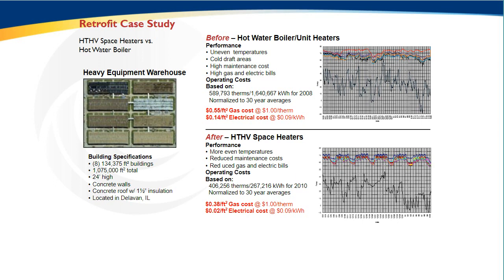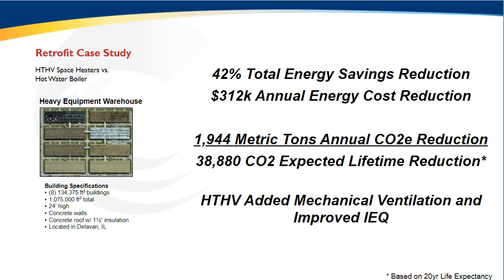And what they saw was they actually retrofitted the entire building with a decentralized HTHV space heater system with more even temperatures, forced mechanical ventilation, and by utilizing the zones and high velocity, they were able to get much more even temperatures, such that they saw a massive reduction in gas and electrical bills. What this facility saw was about a 42% total energy savings reduction. These dollars are quite substantial. Granted, this is a pretty large facility, about 1 million square feet. However, they saw about $312,000 of annual energy cost reduction. And from an emissions perspective, they had almost 2,000 metric tons of CO2 equivalent emission reduction by utilizing the decentralized HTHV system. So again, key theme, added ventilation, improved the indoor air quality, and massive reduction in energy and emissions.